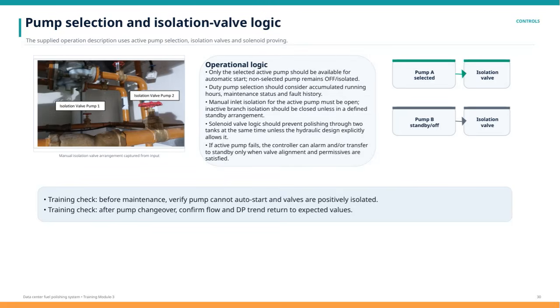Here we're looking at the pump selection and isolation valve logic, which is critical for ensuring safe and efficient operation. The system employs active pump selection, combined with isolation valves and solenoid valve proving, to manage the pumps effectively. Only the pump that's been actively selected should be able to start automatically. Any pumps not selected stay off and isolated to prevent any unintended operation. When choosing which pump to run, the system considers factors like the total running hours, maintenance status, and any fault history. This helps balance pump usage and ensures reliability. The manual isolation valve for the active pump must be open for operation, while the valves on inactive branches should remain closed, except if the system is set up for standby mode.